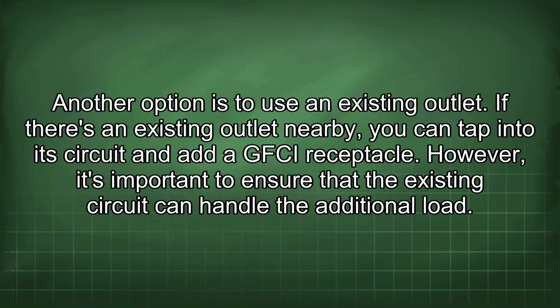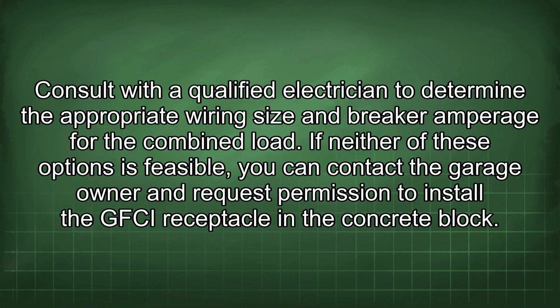Another option is to use an existing outlet. If there's an existing outlet nearby, you can tap into its circuit and add a GFCI receptacle. However, it's important to ensure that the existing circuit can handle the additional load. Consult with a qualified electrician to determine the appropriate wiring size and breaker amperage for the combined load.